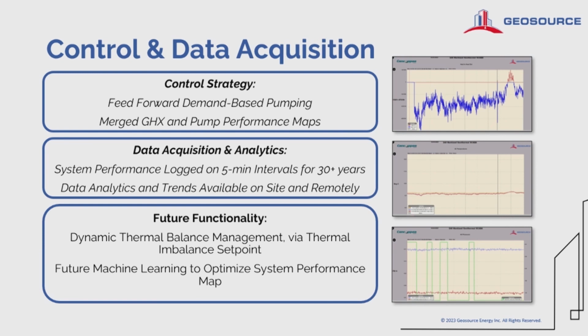We have a single panel for control and data acquisition in this mechanical room. This panel utilizes feed-forward demand-based pumping for control, and merged heat exchanger and pump performance mapping to assist in control as well. The data acquisition and analytics portion of this panel logs data at 5-minute intervals. It will continue logging data for the next 30 years. This data will be used to optimize and ensure efficiency of the system.